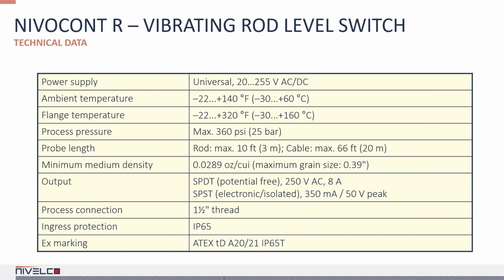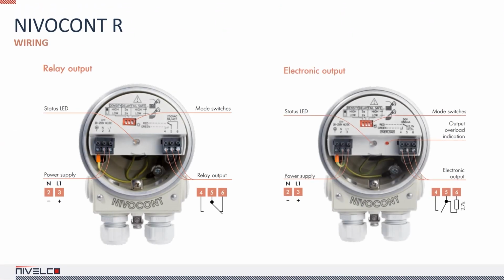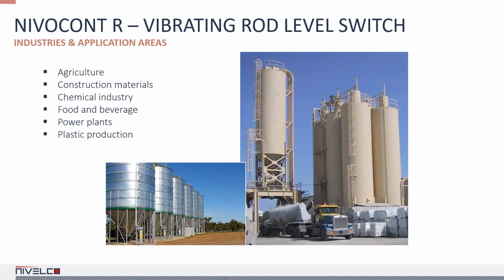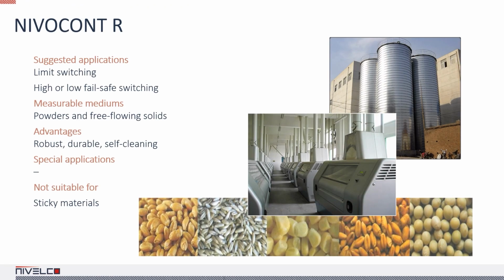The highest flange temperature is 320 degrees Fahrenheit, and the maximum process pressure is 360 psi. The device has an ATEX variant. The device has a relay and an electronic output. Nivocont R switches are used in agriculture, construction, the chemical industry, food and beverage production, power plants, and the plastic industry. They can be used for limit switching and high or low failsafe switching with powders and free-flowing solids.